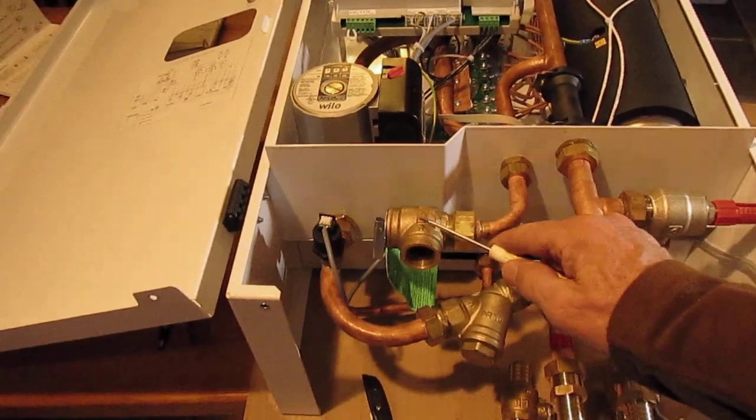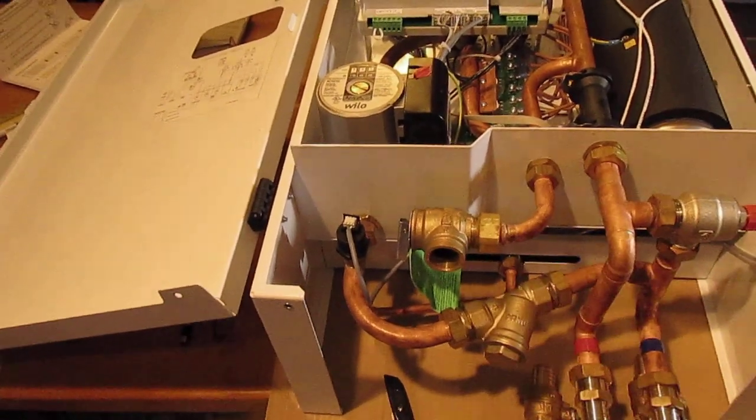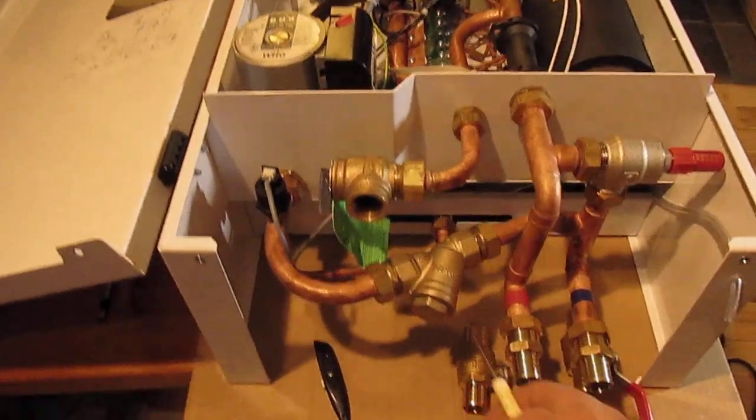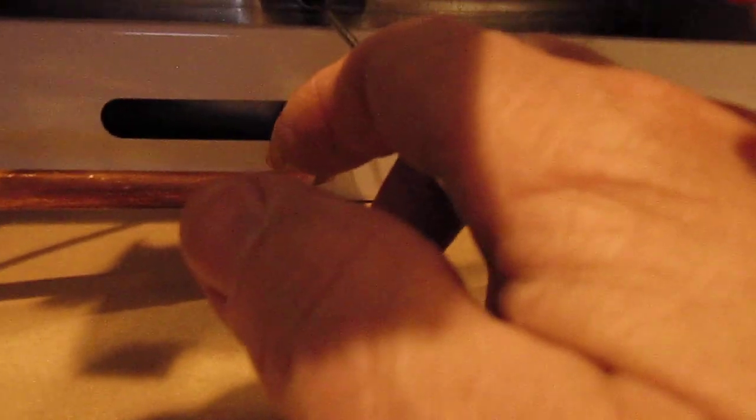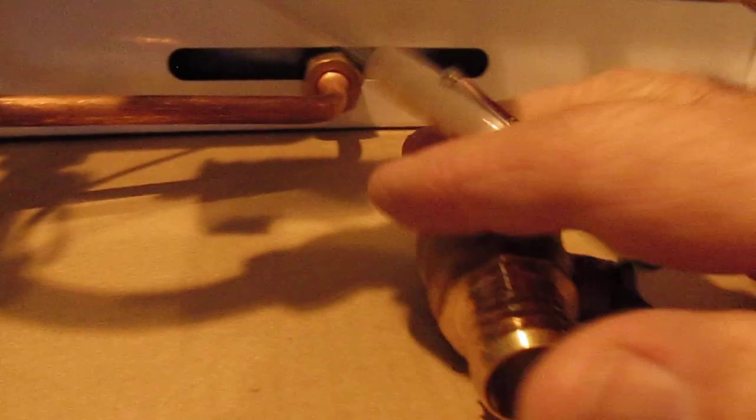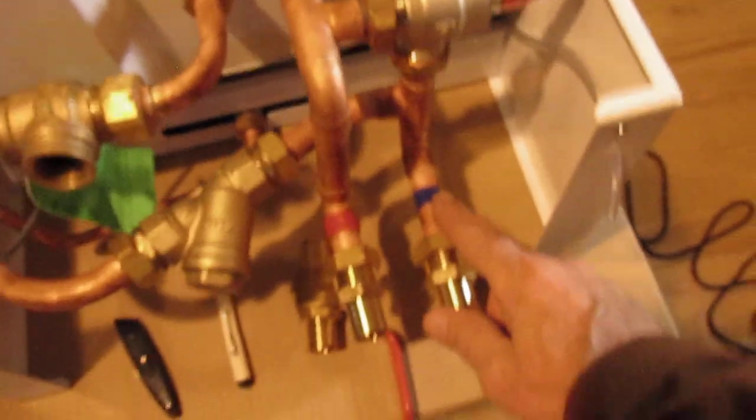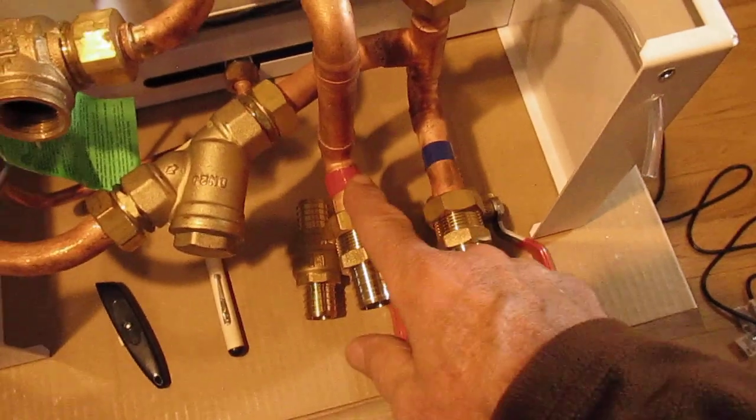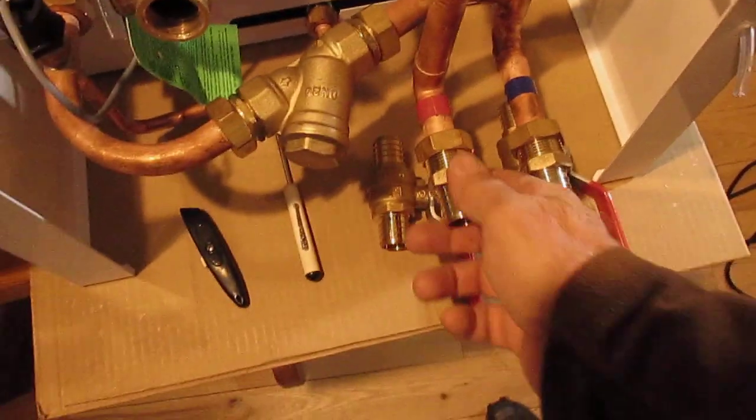And has a pressure relief valve, which is to keep it from blowing up, safety thing. It has an expansion tank down here that has a Schrader valve. Those should be set probably between 15 and 20 pounds or something like that. And it has the connections. Obviously blue is cold, the return which is cold and hot or supply is red.